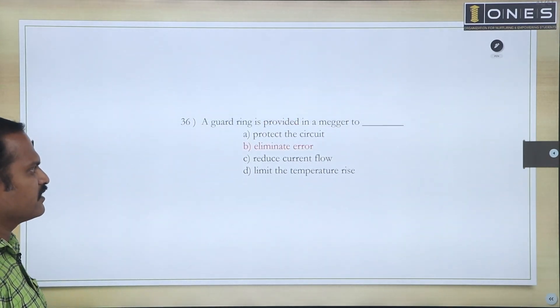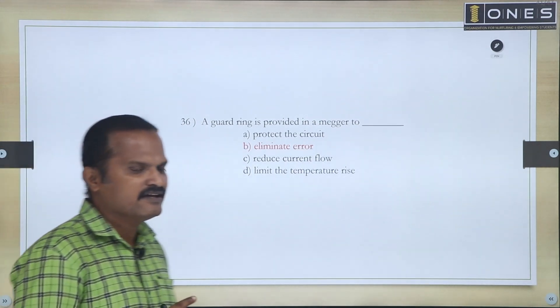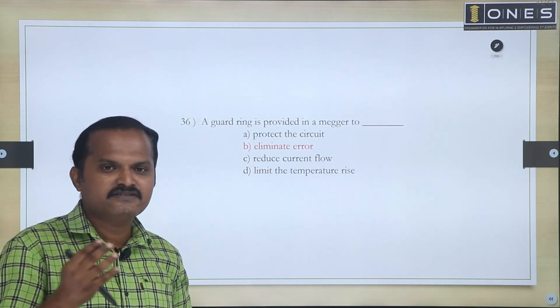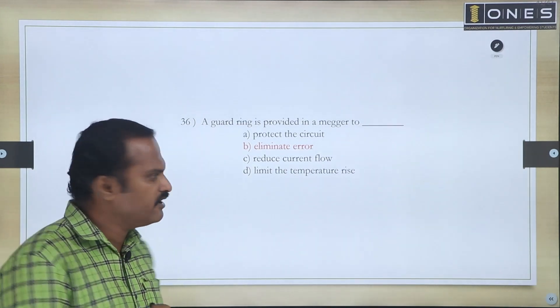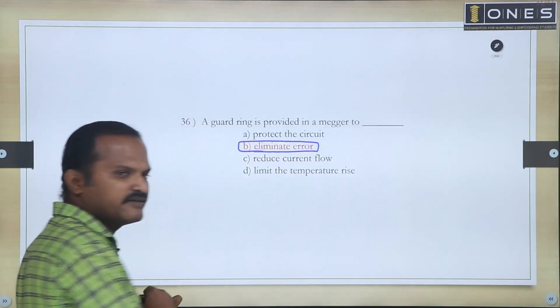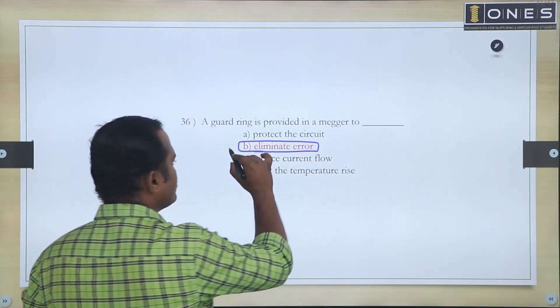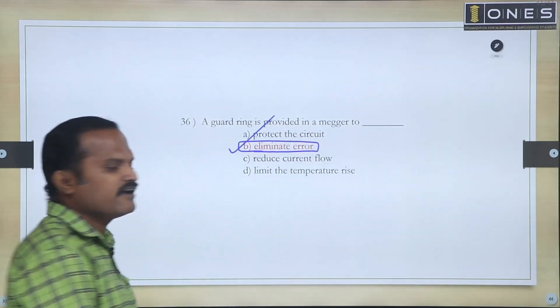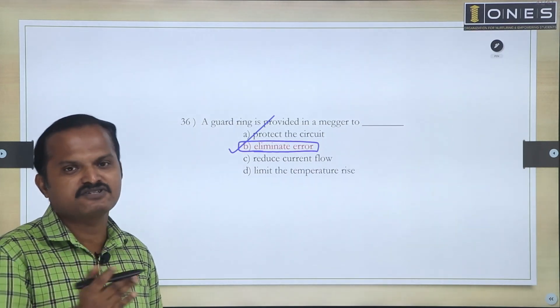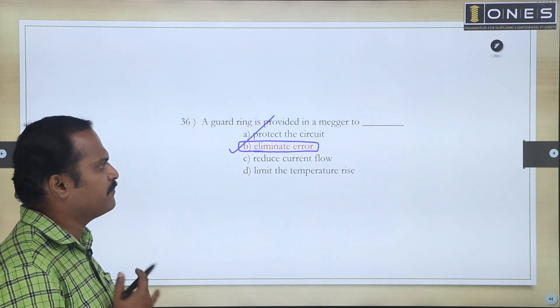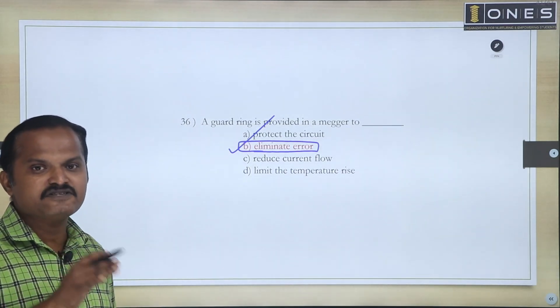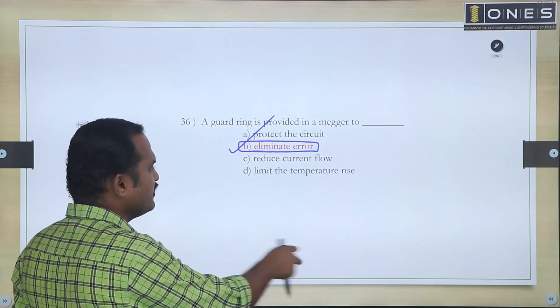Next: The guard ring. The guard ring's main purpose is to eliminate leakage. It will suppress leakage current components to a maximum. It's for eliminating error, minimizing your error while measuring. So the guarding purpose in Megger is to eliminate and suppress your leakage current.